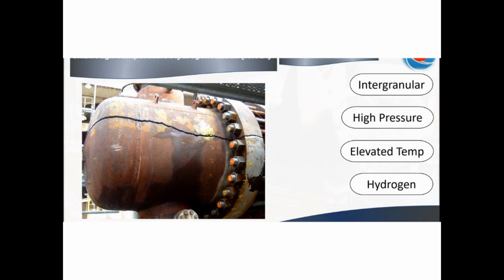First of all, the hydrogen penetrates inside the metal structure, then it reacts with the carbides and carbon present in the metal, and it creates methane gas inside, and the methane gas becomes trapped, and the pressure of the methane gas increases, which will ultimately result in the cracking and damage of the metal. So this was our topic today about high temperature hydrogen attack, which is one of the leading causes of boiler tube failure.